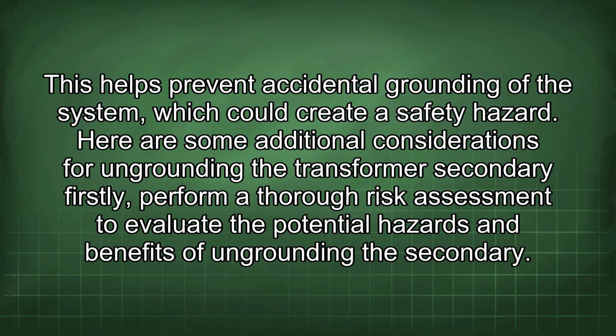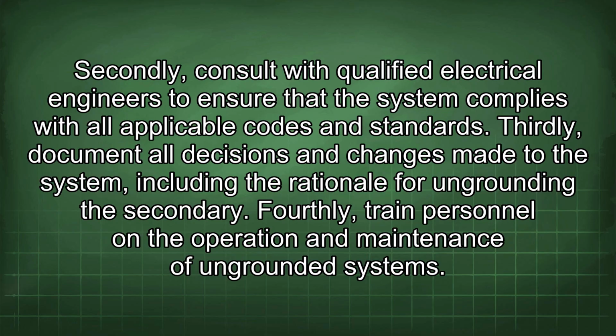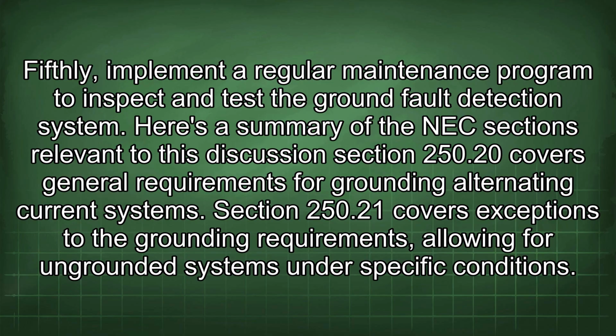Here are some additional considerations for ungrounding the transformer secondary. Firstly, perform a thorough risk assessment to evaluate the potential hazards and benefits of ungrounding the secondary. Secondly, consult with qualified electrical engineers to ensure that the system complies with all applicable codes and standards. Thirdly, document all decisions and changes made to the system, including the rationale for ungrounding the secondary. Fourthly, train personnel on the operation and maintenance of ungrounded systems. Fifthly, implement a regular maintenance program to inspect and test the ground fault detection system.